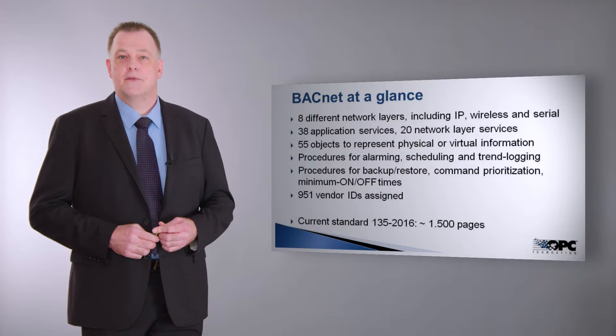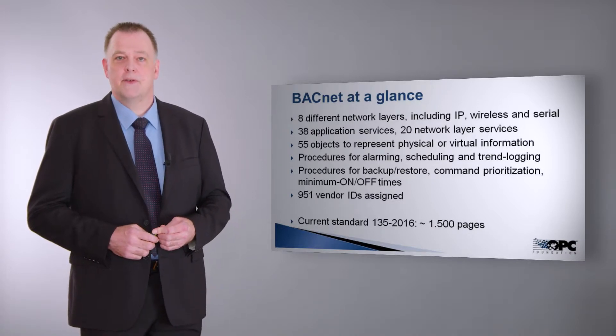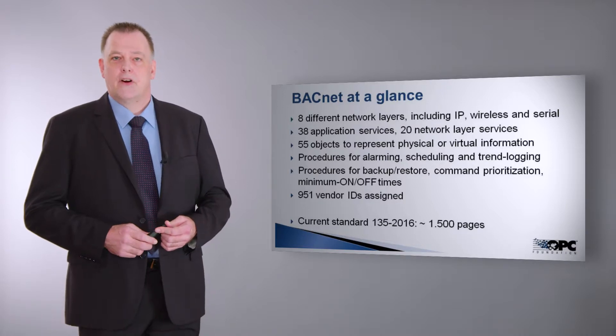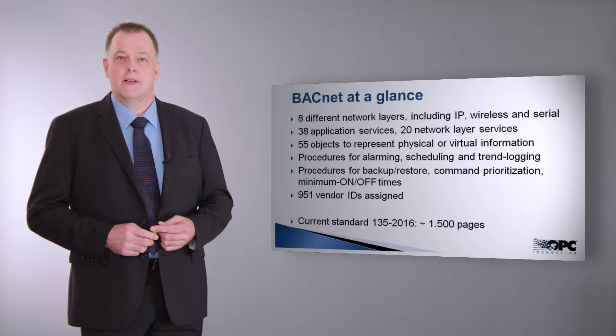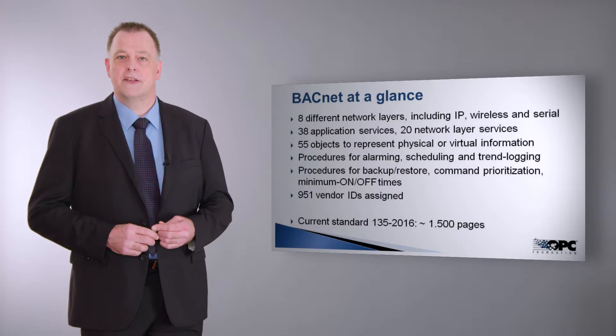BACnet International and BACnet Interest Group Europe are the two driving forces to market the BACnet standard worldwide. BACnet is an international standard in ISO norm 16484 part 5 and part 6. BACnet specifies a total of eight different network media including the IP protocol. 38 application services are used to transport the data, from simple reading to writing up to file transfer or alarm transmission. At the moment there are 55 BACnet objects specified to represent the data from building automation systems. BACnet also specifies procedures for how to prioritize commands, how to back up and restore systems, or presenting state text information.